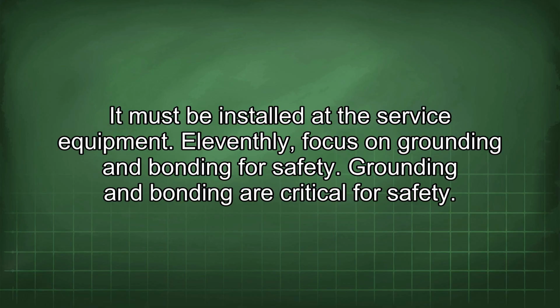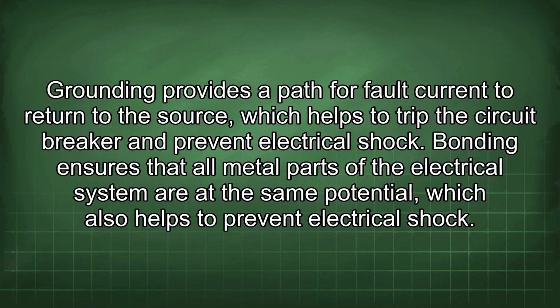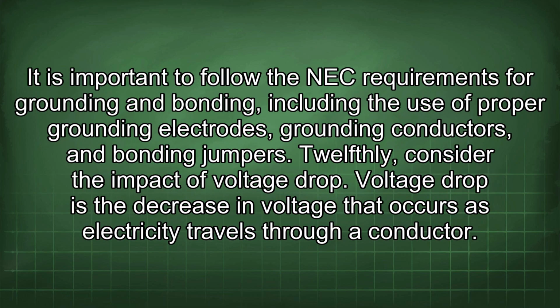11thly, focus on grounding and bonding for safety. Grounding and bonding are critical for safety. Grounding provides a path for fault current to return to the source, which helps to trip the circuit breaker and prevent electrical shock. Bonding ensures that all metal parts of the electrical system are at the same potential, which also helps to prevent electrical shock. It is important to follow the NEC requirements for grounding and bonding, including the use of proper grounding electrodes, grounding conductors, and bonding jumpers.